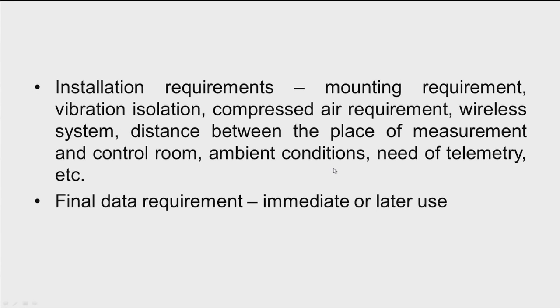Installation requirements must also be considered — how the instrument is to be mounted, whether a magnetic stand, column, or vibration isolation system is required, or whether compressed air is needed (for example, air gauges require compressed air). We should also consider whether wireless systems are required, what the distance between measurement location and control room is, and what the ambient conditions are — temperature, pressure, humidity, or whether measurements are required underwater or in space.